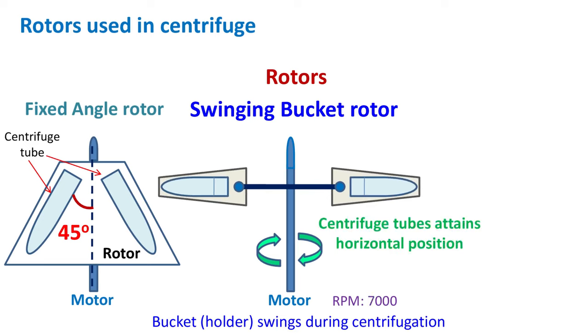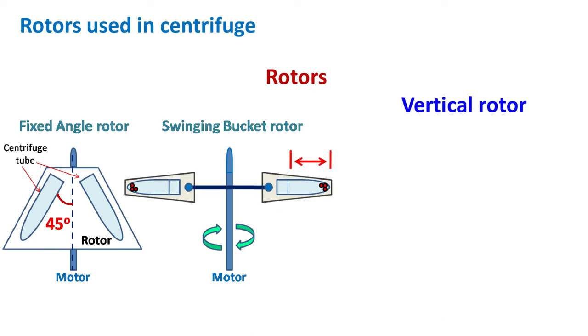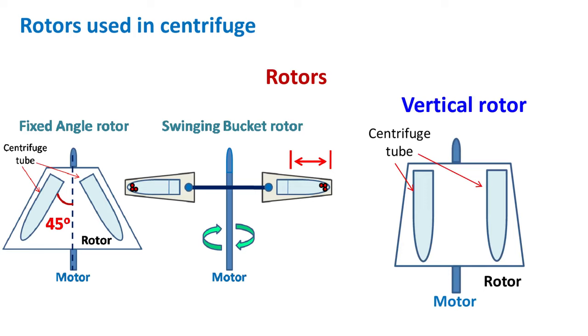Because of this, the path length traveled by the particles is maximum. The particles also take long time to settle as it travels from the top to the bottom of the tube. In vertical rotors, the centrifuge tubes are held in vertical position. Here the path length traveled by the particles is minimum as they are moving from one side of the tube to the other and not from the top to bottom. The particles are usually accumulated on the side of the tube.